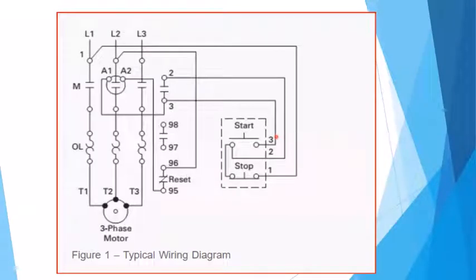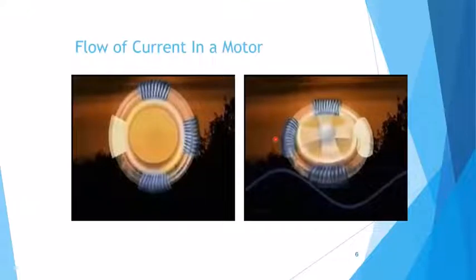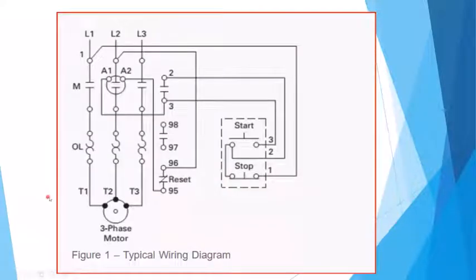So the beginning of it typically is that when they apply the power to the motor, creating the sine wave is here, which is like the voltage or input source. You have line 1, 2, and 3, which is your 3-phase power. I'm not going to go into single phase, as we could do that another day. It's a little bit more complex, but what we're doing is still creating a rotating field. So you have phase 1, 2, 3. They have just a set of contacts here as the old starters, and you turn that on, and then this is the overload. They're like thermal coils that sense how much current's going through there.